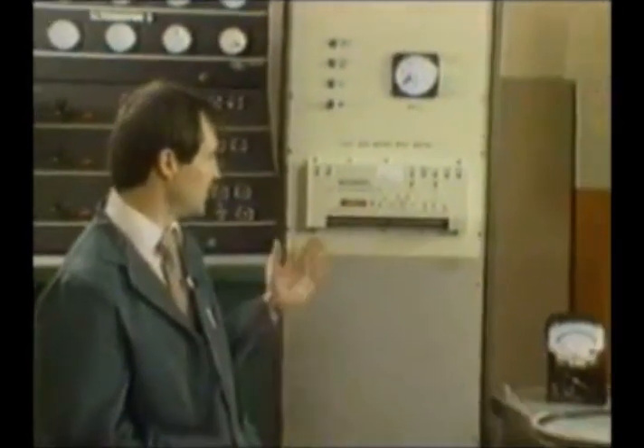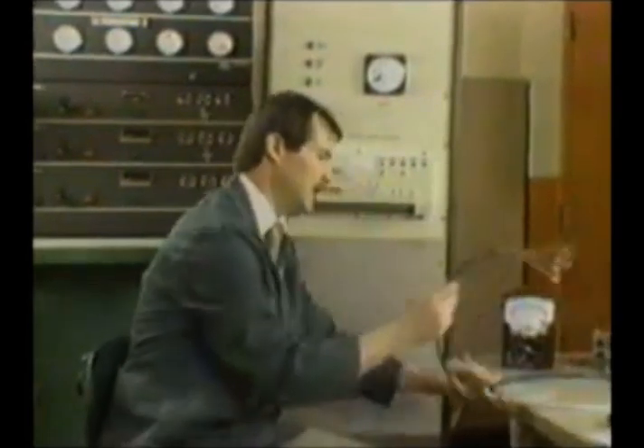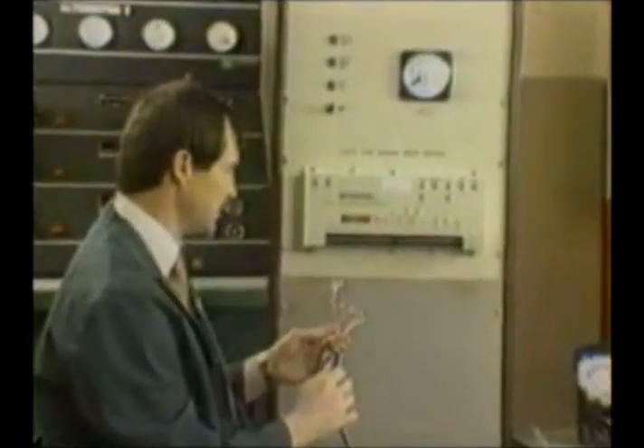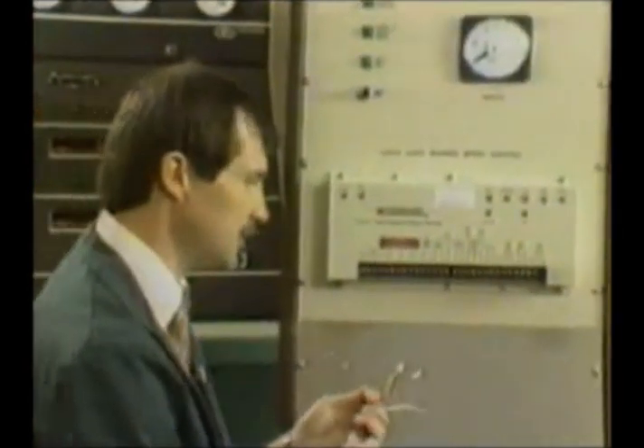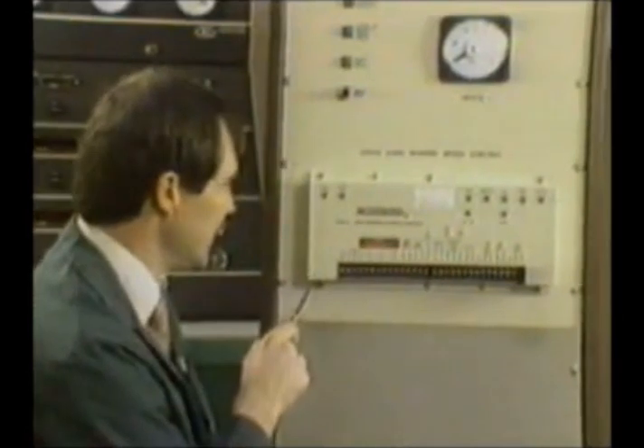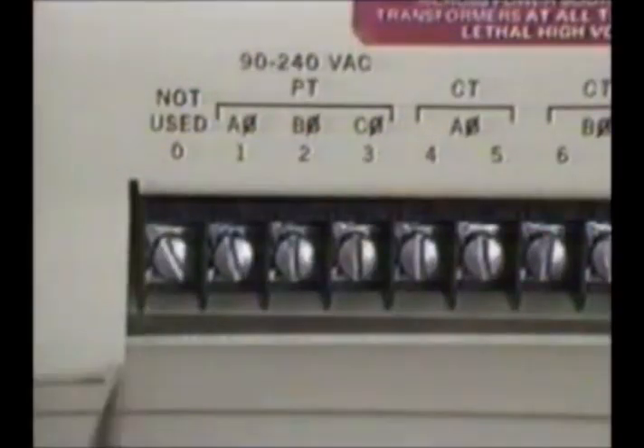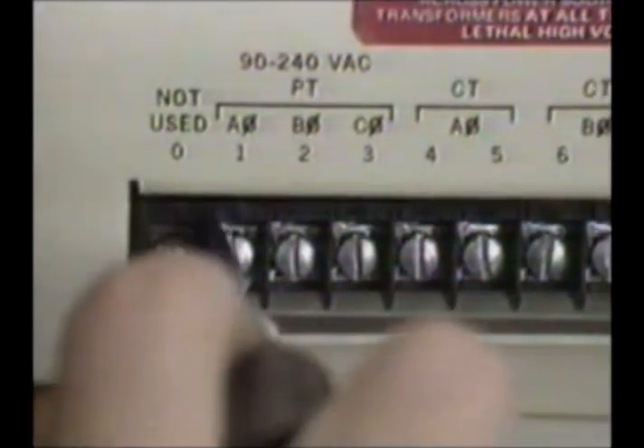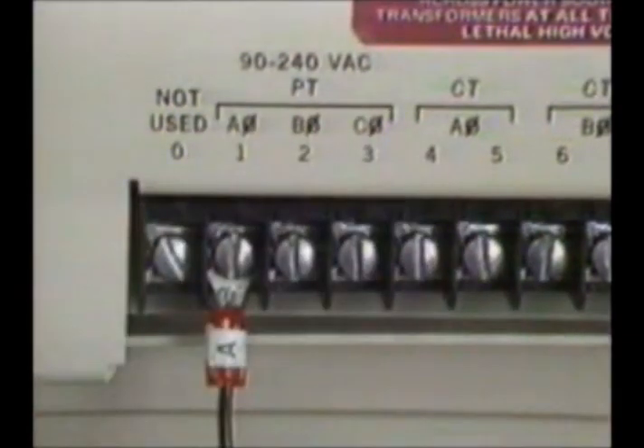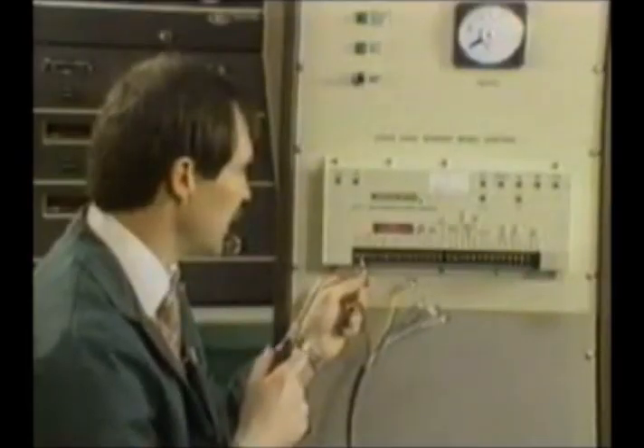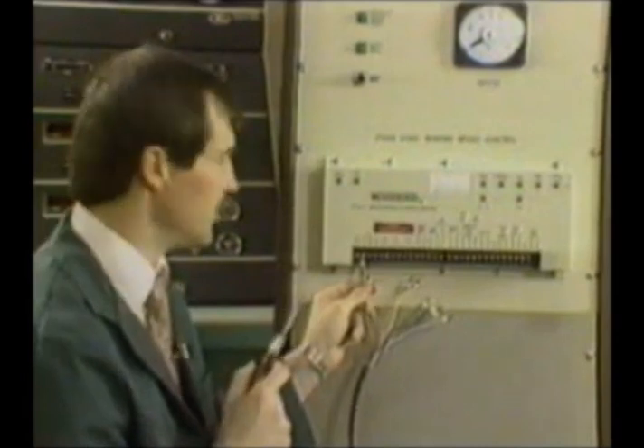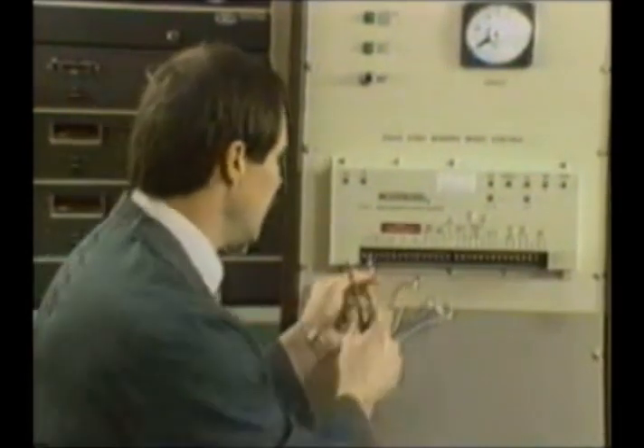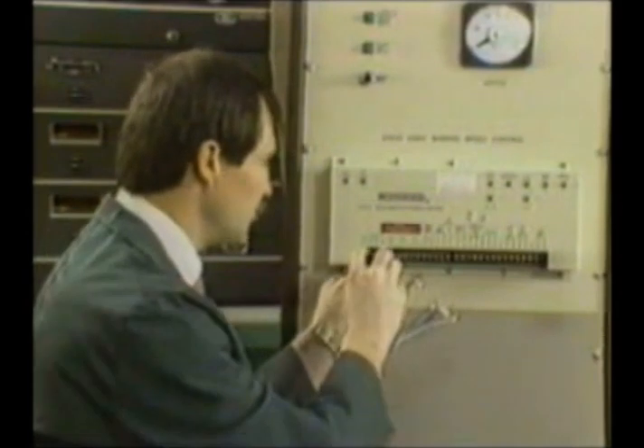So we're going to start wiring to the control. We're going to hook up our PTs and CTs first. I have my wiring coming out here, and my PTs and CTs are all in a bundle by themselves, and I have them labeled, and they're also color-coded. I'm going to start by connecting up. You have to make sure you don't use terminal 0. So make sure that you start hooking the A-phase potential transformer to terminal 1. The potential transformers are designed to run at a minimum of 90 volts AC and to a maximum of 240 volts AC. So make sure the signal you're providing us falls within that range.